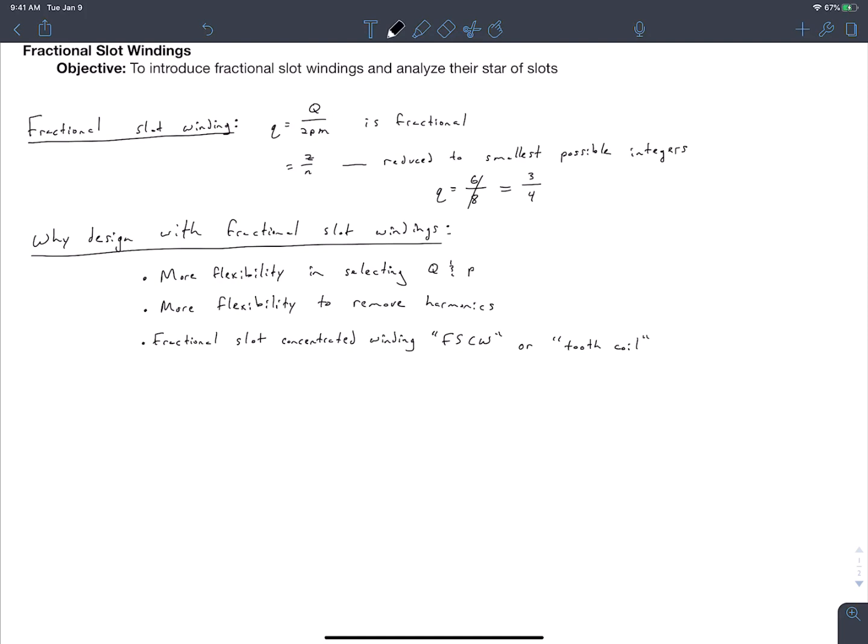The third reason is that you can develop what's called a fractional slot concentrated winding, or FSCW, also referred to as a tooth coil. A fractional slot concentrated winding is a coil that only spans one slot — it's wrapped directly around a tooth. This is a very convenient winding for manufacturing. You could pre-wind your coils on bobbins that you directly slide onto the teeth, or have a custom lamination where you wind coils onto teeth that you bolt onto the stator laminations. This also allows you to have a higher slot fill factor — you can pack more coil sides into a slot.